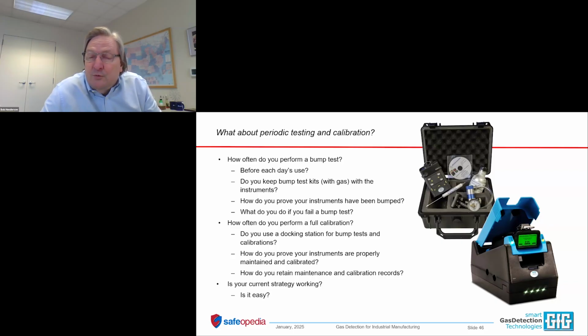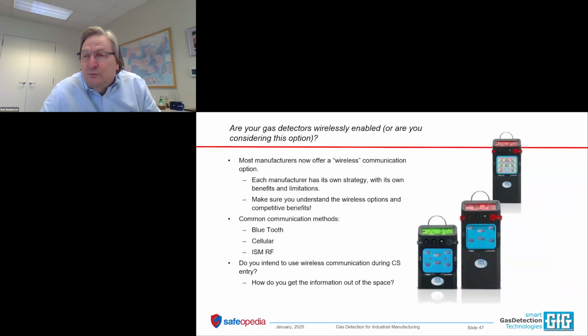If you're dealing with the instruments by checking them out of a tool room in the morning, then having a docking station in the tool room really makes a lot of sense. So before they leave the tool room, you put them in the dock, you verify the instrument is fit for use, and off you go. For fixed gas detection systems, it's not a daily occurrence. You're probably going to do a full calibration, usually on a quarterly basis, or if something unusual has happened.